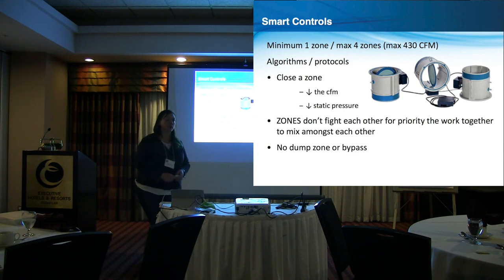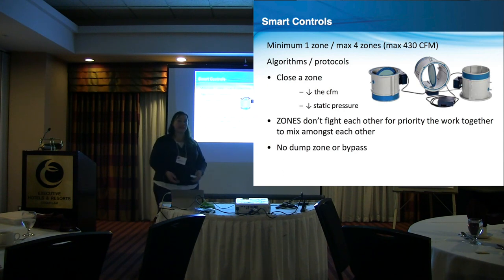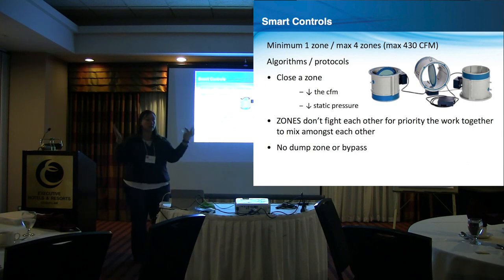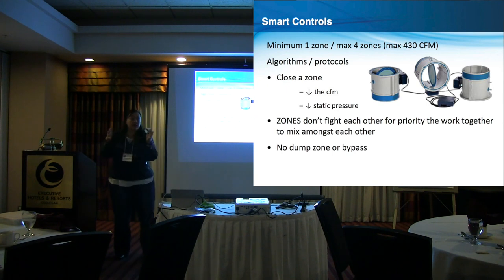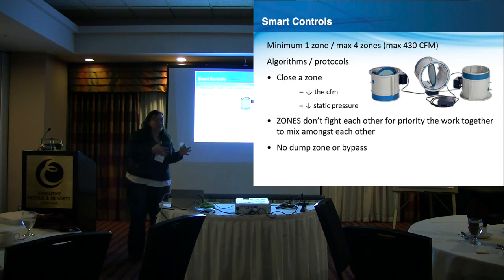So fundamentally, it's kind of taking a step backwards every time, right? We pick the equipment, then we look at what each room needs, then figure out what you need. With the zoning system now, we know 8-inch, 430 CFM per zone. So we need that 60,000 BTU furnace. We're not going to put in a 75 because we need those CFM to be the right CFM. It makes sense now.